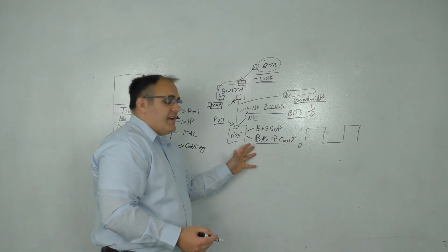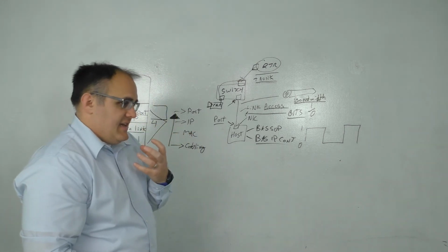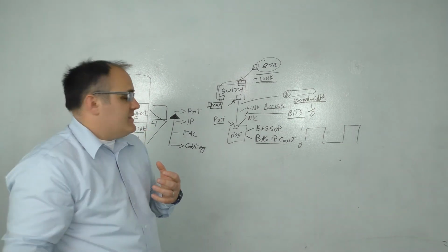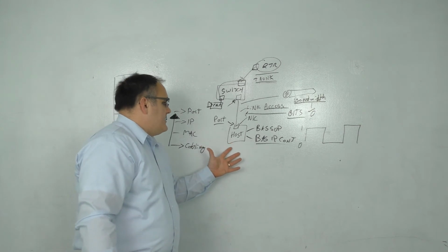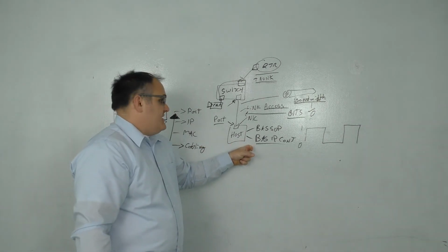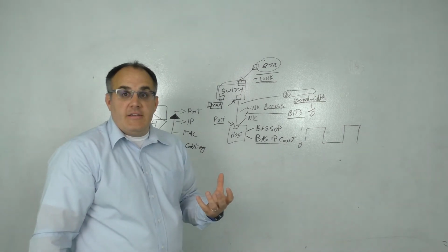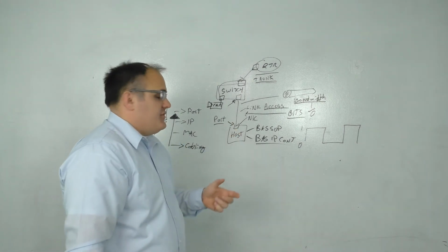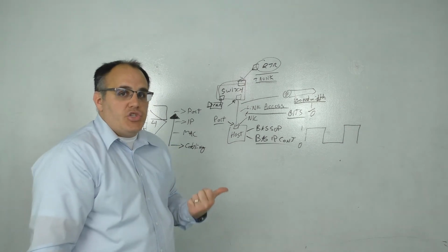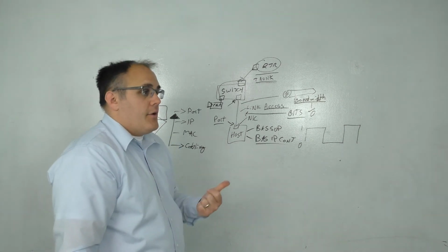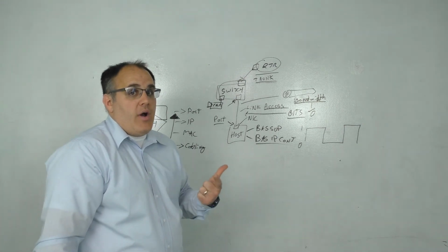So when you're looking at this, what I want you to see, as a BAS professional talking to another BAS professional, is: all right, I've got my BAS device and it's got a network interface card on it. And I plug my cable into it, and I've got to make sure that my electrician terminated those cables right and that they followed the right wiring standard as to where the wires go.